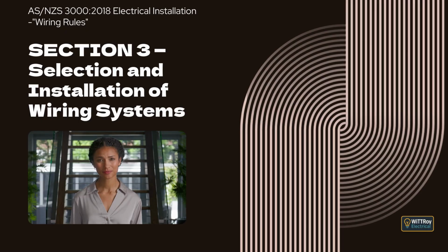Clause 3.9.8.3, Segregation of different voltage levels. This clause explains that high voltage, low voltage, and extra low voltage circuits must be segregated unless specific insulation or physical separation arrangements are used. Clause 3.9.8.4, Proximity to non-electrical services. This clause explains separation requirements between electrical wiring and services such as gas, water and telecommunications, including minimum separation distances and applicable New Zealand requirements.